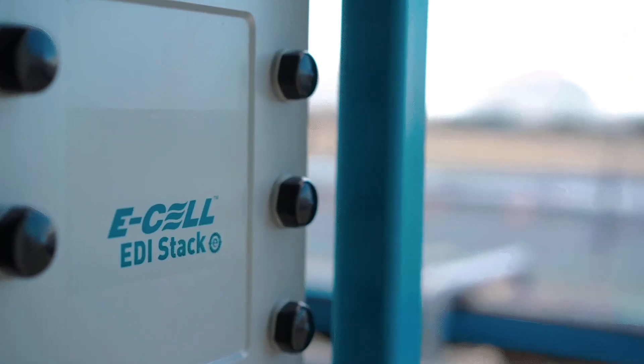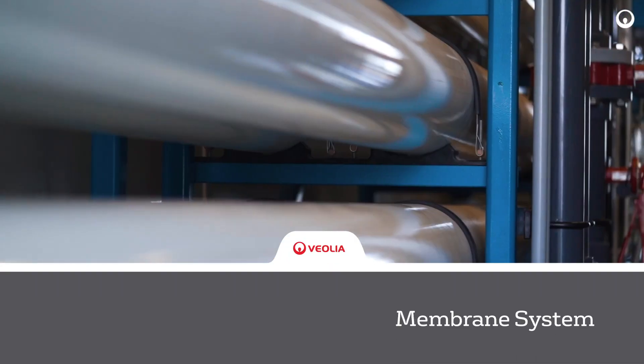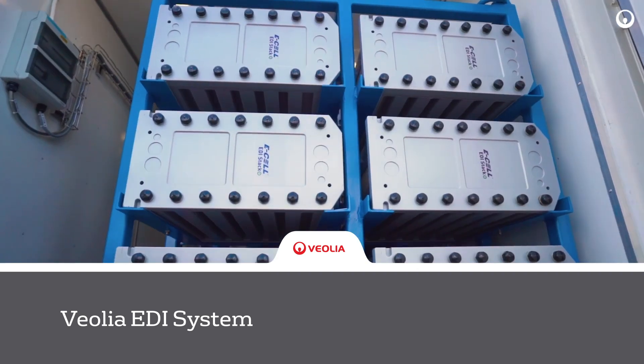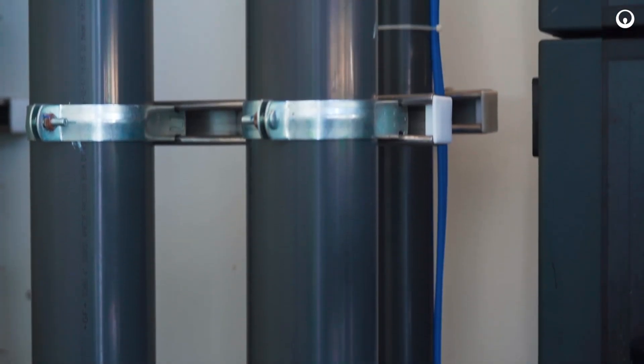The units are equipped with Veolia's pre-treatment filtration system followed by a combined reverse osmosis and electro deionization EDI system, which produces ultra pure makeup water to be used in the boiler feed water.